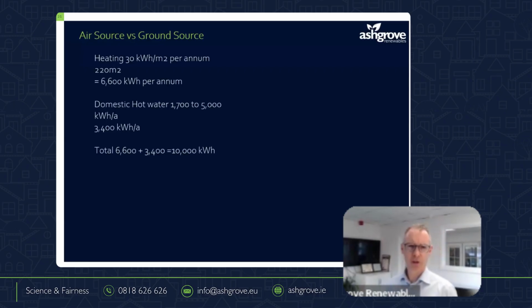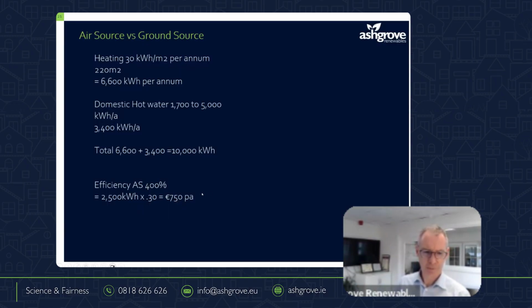Air source versus ground source, just the maths on it. In domestic housing, we won't go down through what we just did above. This is a slide I stole from something else. 10,000 kilowatt hours here, we're assuming, is a kind of a standard house for heating and hot water. With an air source heat pump with a COP of 4, electricity at 30 cents is €750. If I go with ground source, because I have a higher efficiency, I need to buy less from the grid. At 30 cents is €600. So yes, it's more efficient. It's saving me €150 a year.